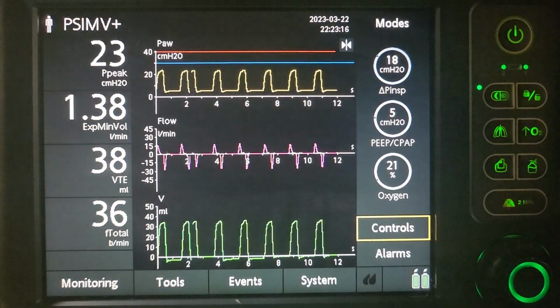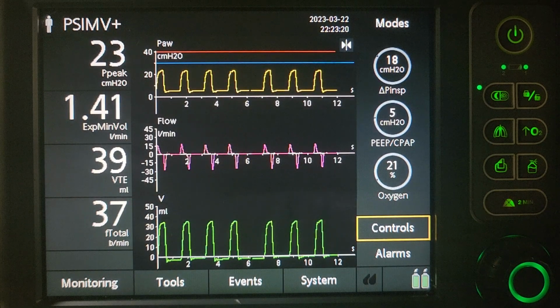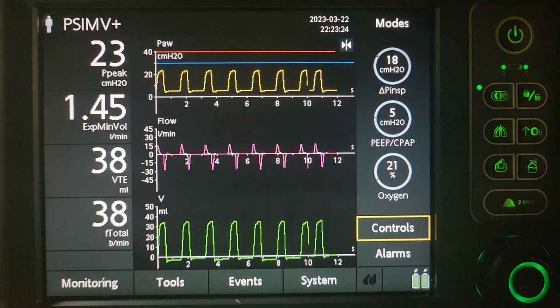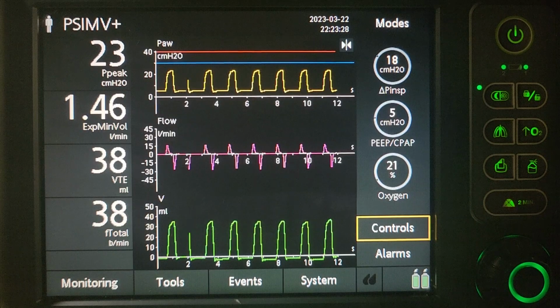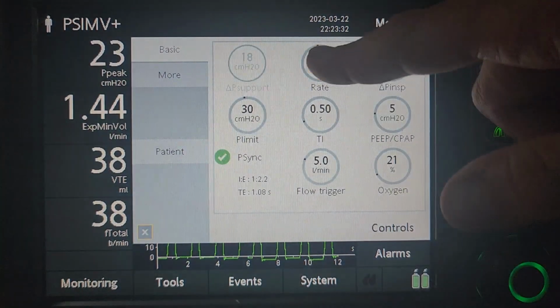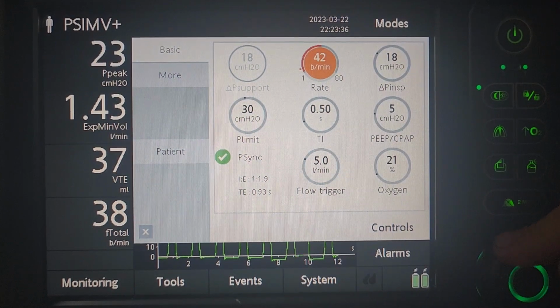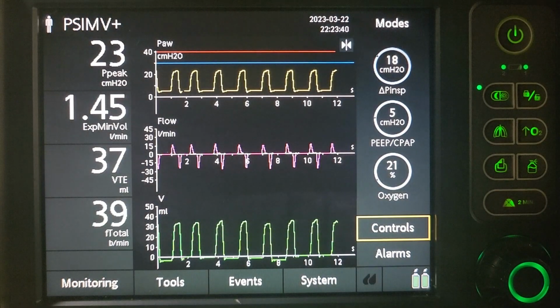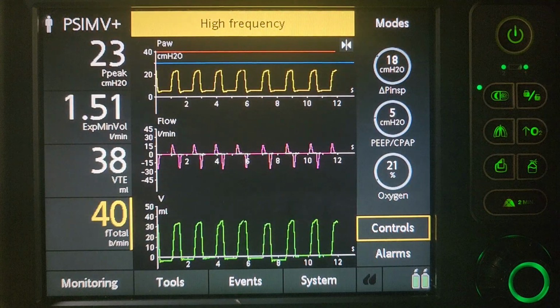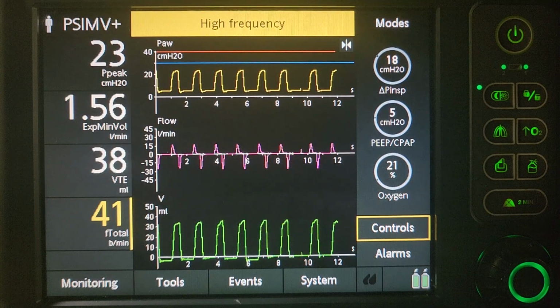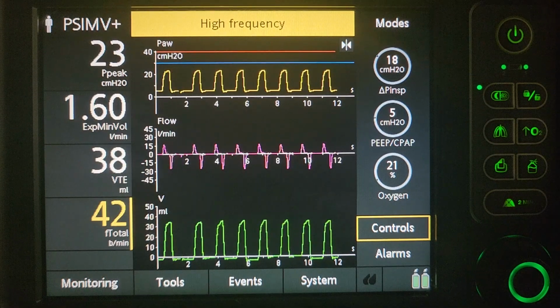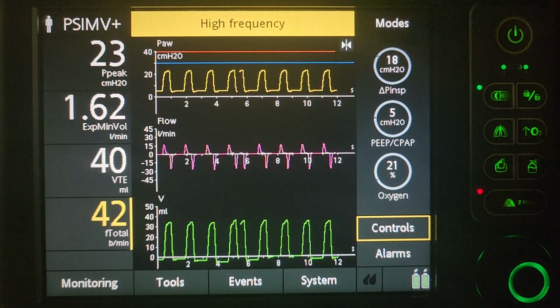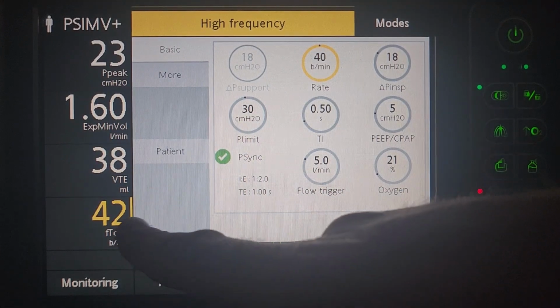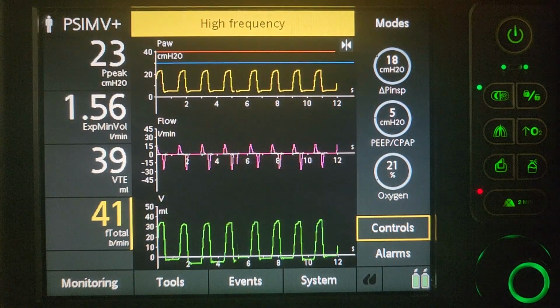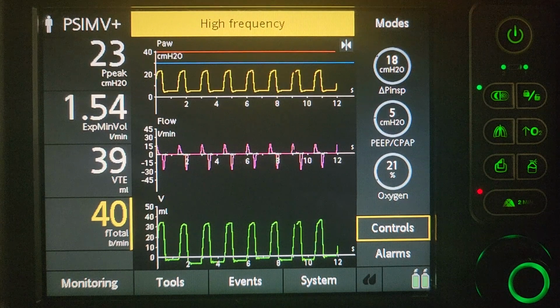Once we increase that, let's go back and make sure we're not stacking any breaths and we're not trapping any air. We still have room to work. So if we like the tidal volume, our pressures are good, we can increase that rate even further. So we can go back into controls and look at our expiratory minute volume increasing. So we're at 1.6. This is only if we need to blow off excess CO2 for those severe metabolic acidosis patients. So typically 200 per kilo, 5 kilos, that would be a 1 liter expiratory minute volume.